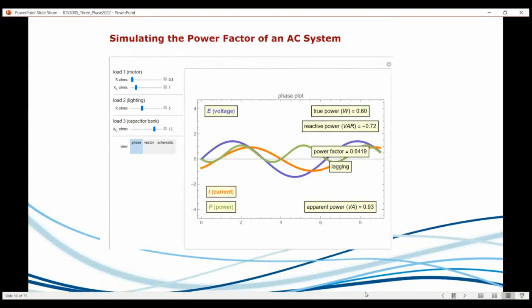Another benefit is reduction in bills. Typically, if you own a factory, you get charged for kVA and not for kilowatt like normal consumers - this doesn't apply onboard a ship, but it applies to the first point I mentioned. Consequently, we also have extra kVA available for the supply, so if we improve the power factor, we can actually generate more power. They also mention reduction of I squared R losses in transformers and distribution equipment, and reduced voltage drop in long cables in particular. So there are a few benefits on why you want to improve power factor.